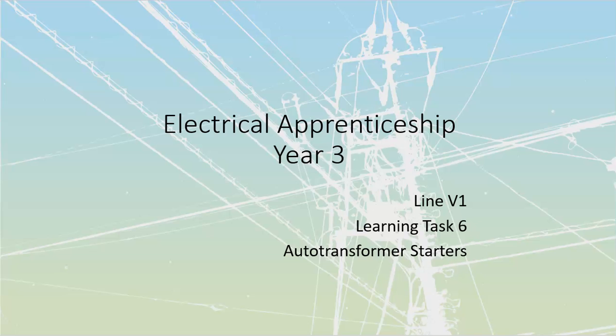All right, line V1, learning task number 6. We're going to take a look at autotransformer starters. An autotransformer starter is just going to be another way that we can have a partial voltage start on a motor, which once again is going to decrease the amount of inrush current that we are going to have.